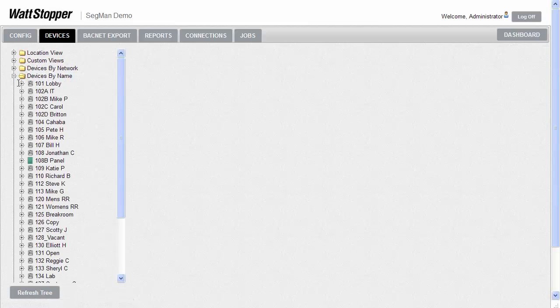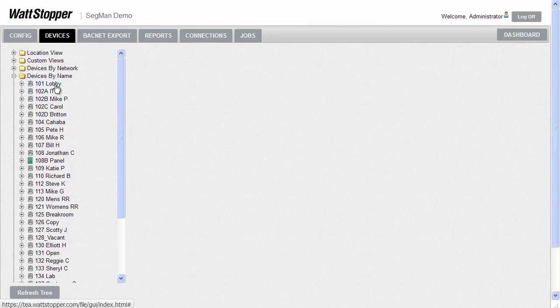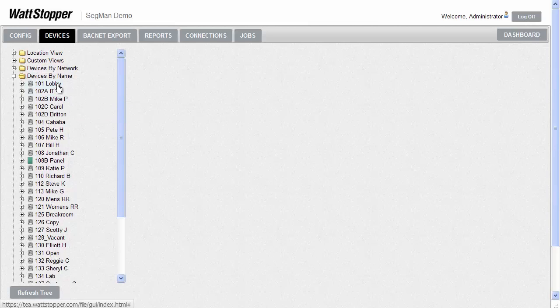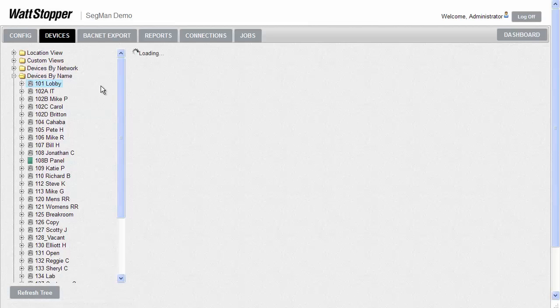For this Segment Manager, all the name fields have been filled in with the office number and employee's name, and so they're all arranged based on that text info. In a new installation, instead of seeing names of all the rooms like you see here, you'd see the device tree with all network bridges arranged based on their serial numbers. In that case, somebody would have to go through and, using a cross-reference that hopefully would have been prepared by the contractor or the startup technician, they would click on every individual bridge in a room and type that room's name and number, as well as any other key information.